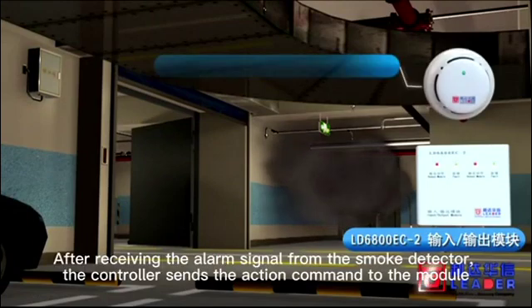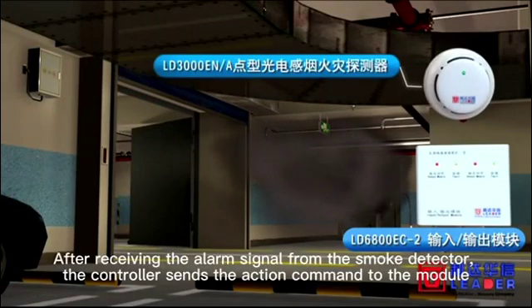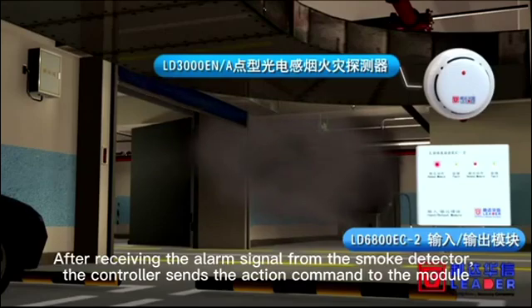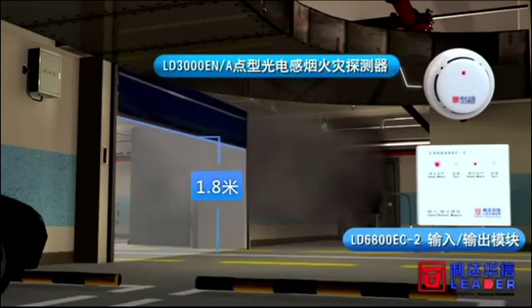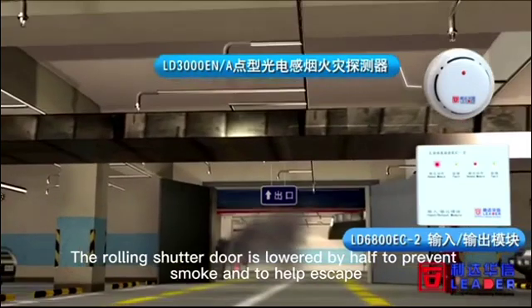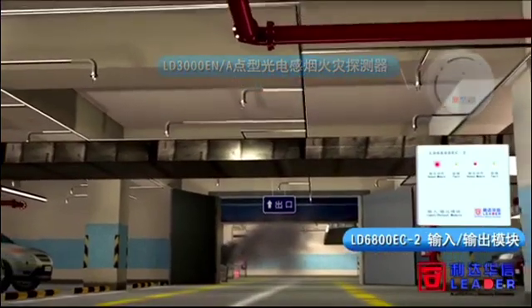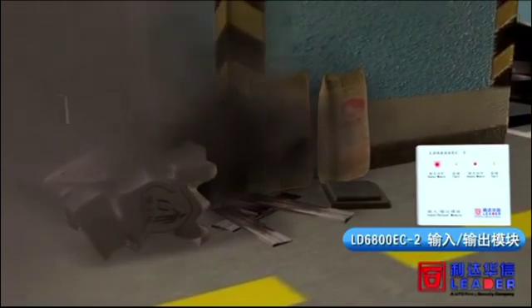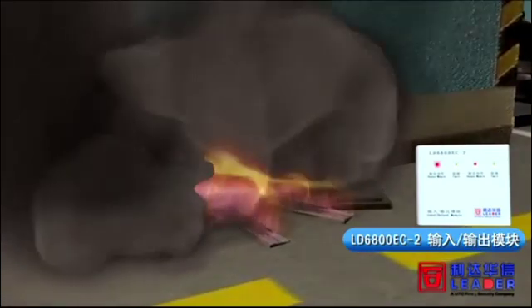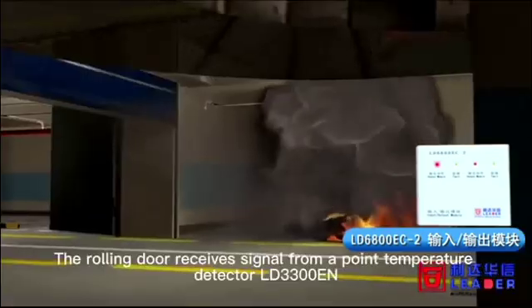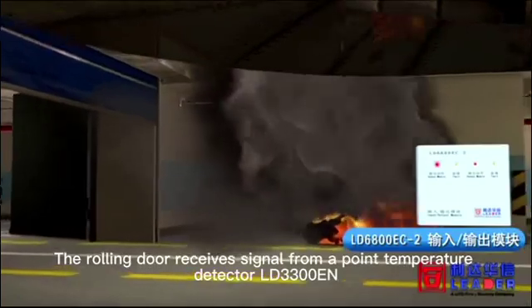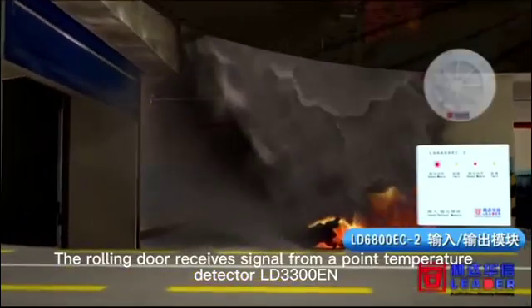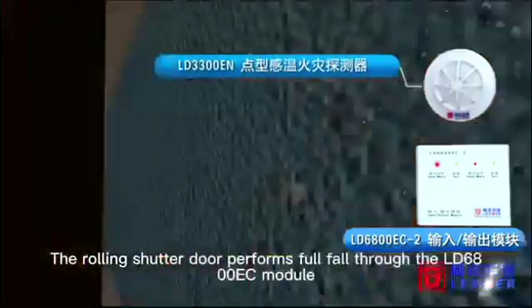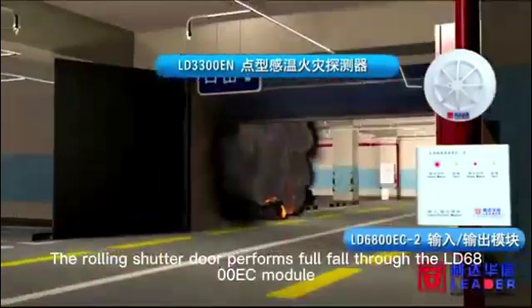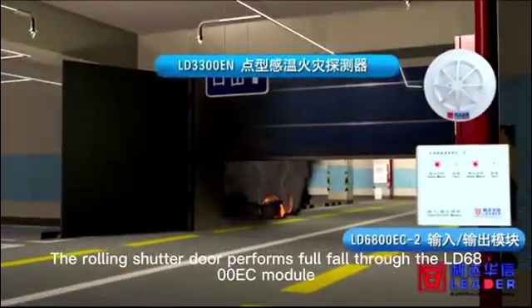After receiving the alarm signal from the smoke detector, the controller sends the action command to the module. The rolling shutter door is lowered by half to prevent smoke and help escape. As the fire grows, the rolling door receives a signal from the point temperature detector LD3300EN. The rolling shutter door performs a full drop through the LD6800 EC module.